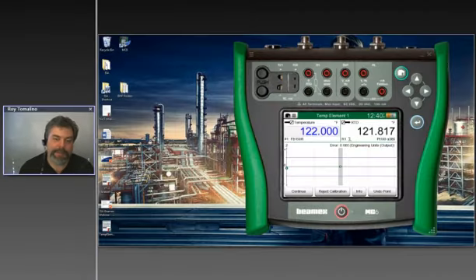So back to my calibration. You can see the MC6 on the screen, and we're at our middle test point. We're going 32 to 212. Again, it's freezing to boiling, and I'm just doing a 3-point test from that range. And let me hit continue. I had paused it so it didn't go, because this is set up for an automatic calibration. And I've only got a 5-second delay set up in between these steps, and I would probably put a 3 to 5 minute delay just so there was more time to stabilize the temperatures.